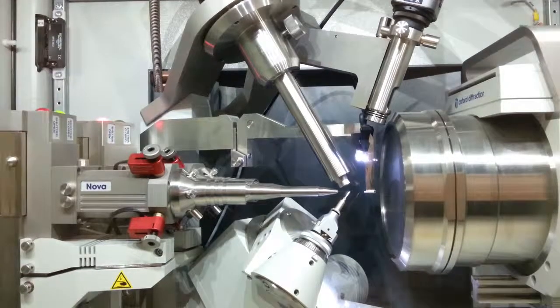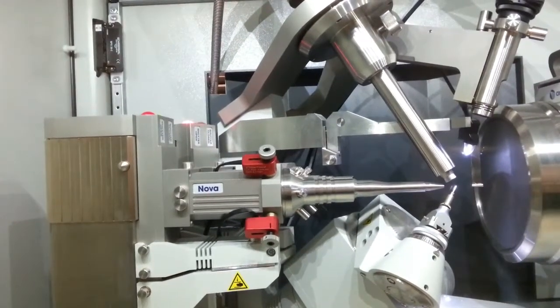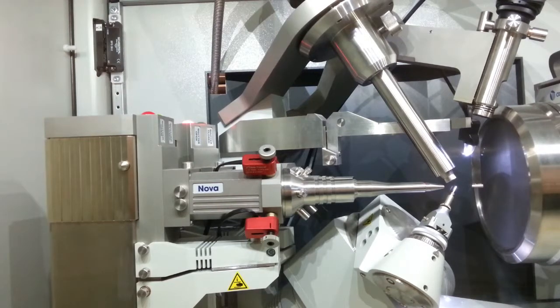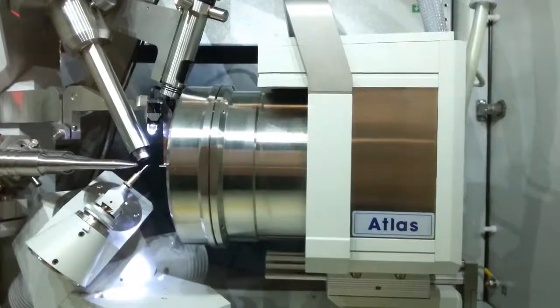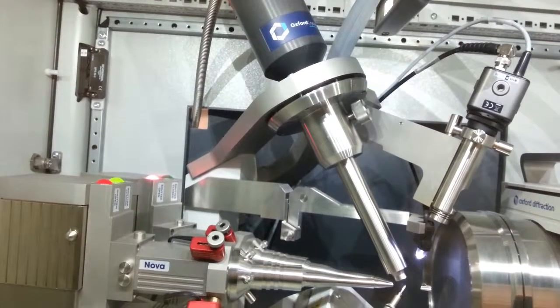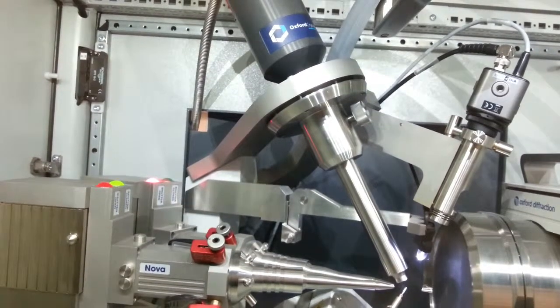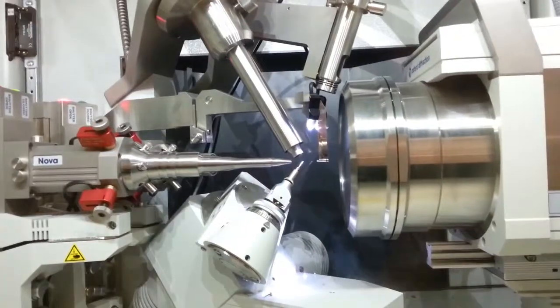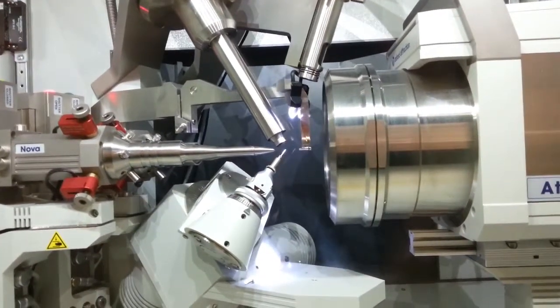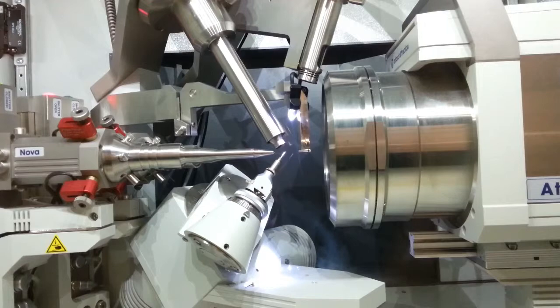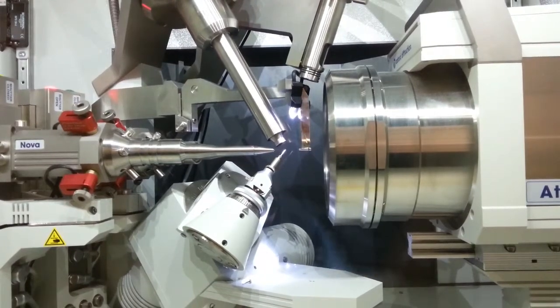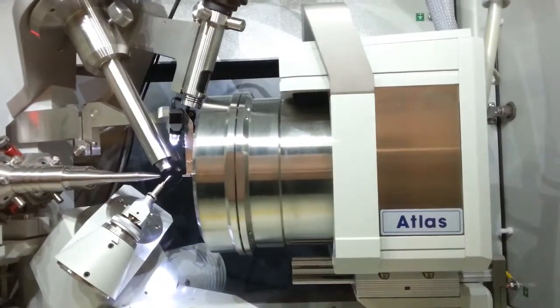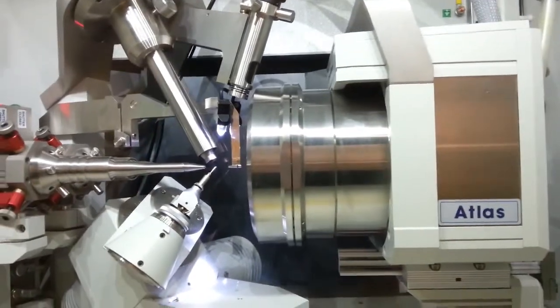Okay, that's this one over here. You see where it says Nova? Yeah, that's the tube. So the X-rays are made kind of behind that, kind of underneath that red light that's on at the moment. Atlas is your detector. The X-rays shoot along that little tube and hit the crystal. You can see gas or steam coming off it. That's not liquid nitrogen, but gaseous nitrogen. You use a thing called a cryostream, which chills the crystal.